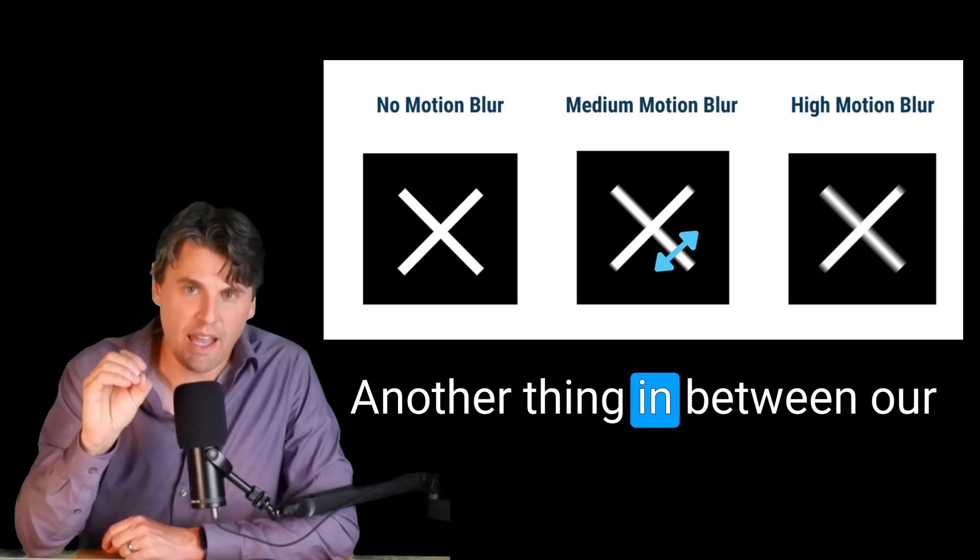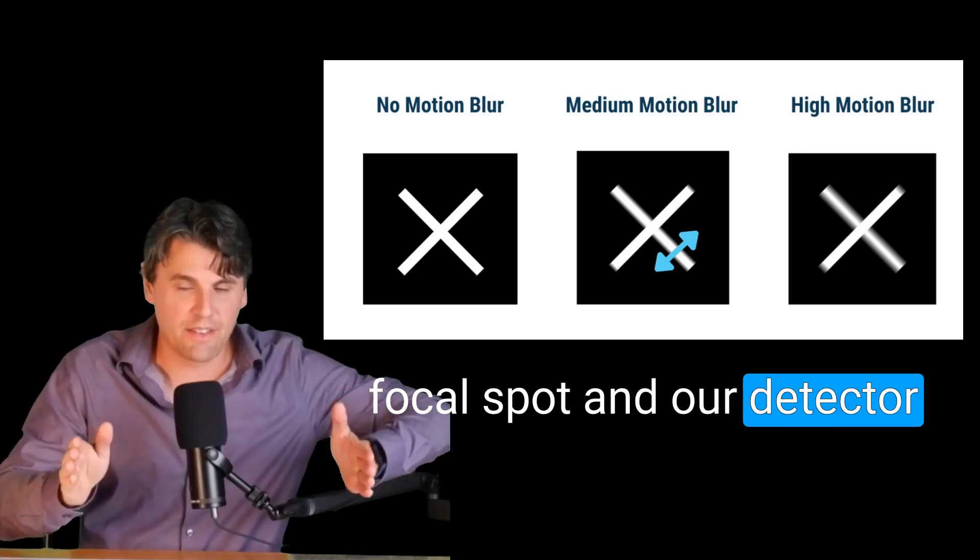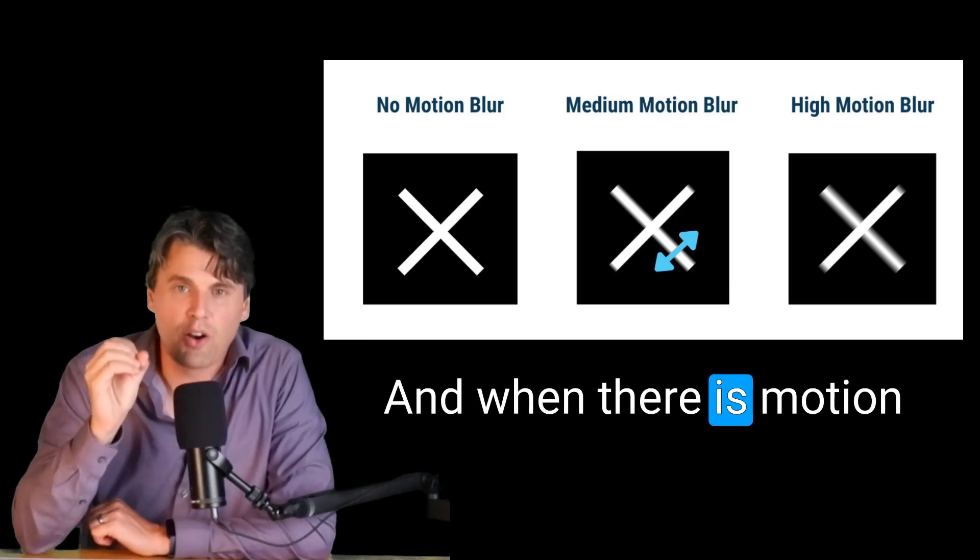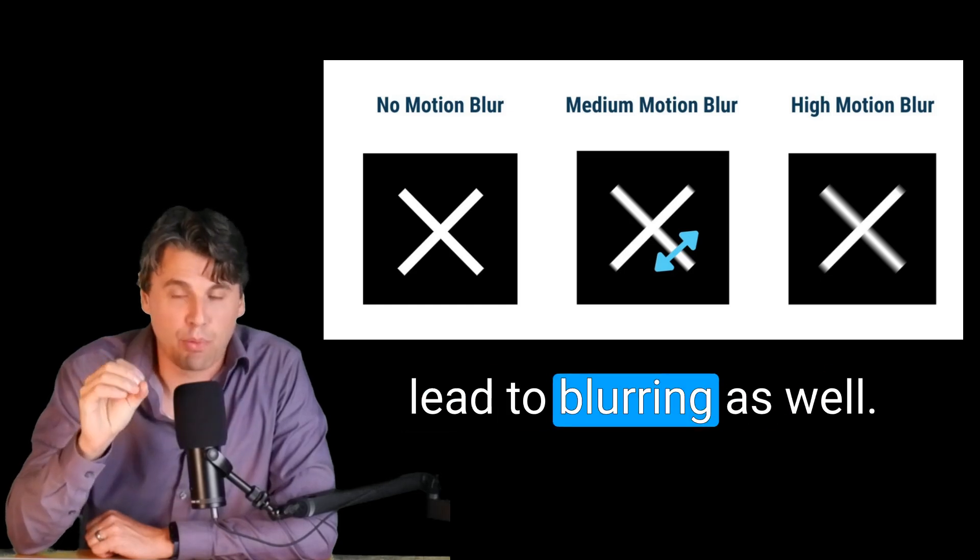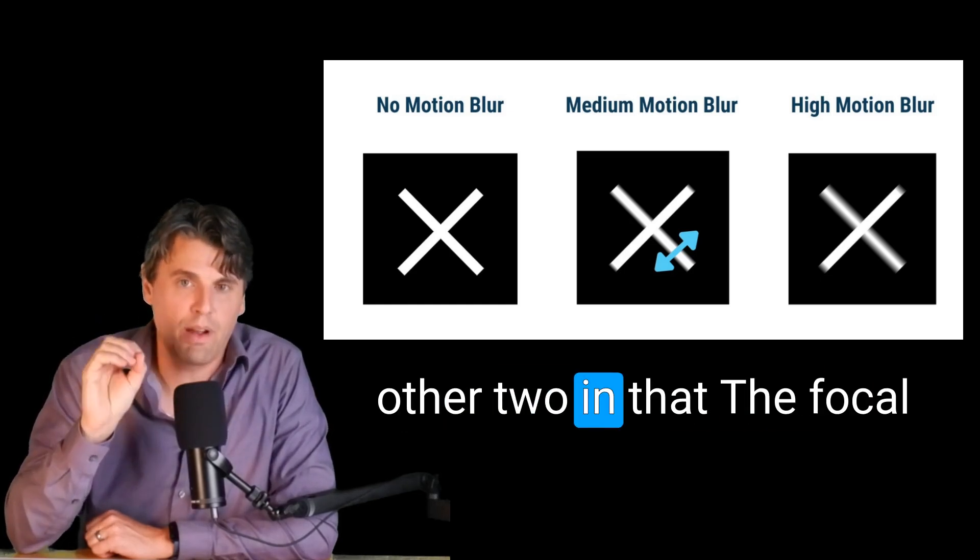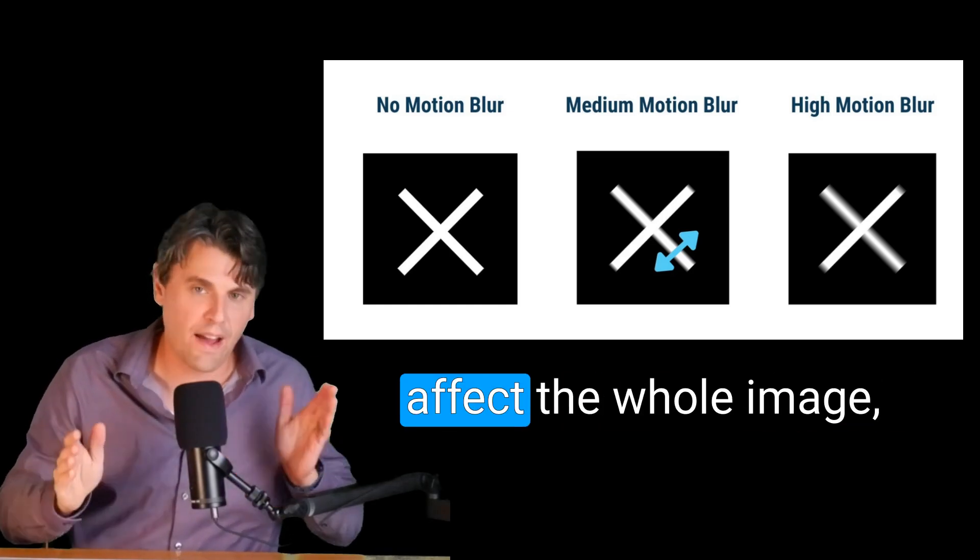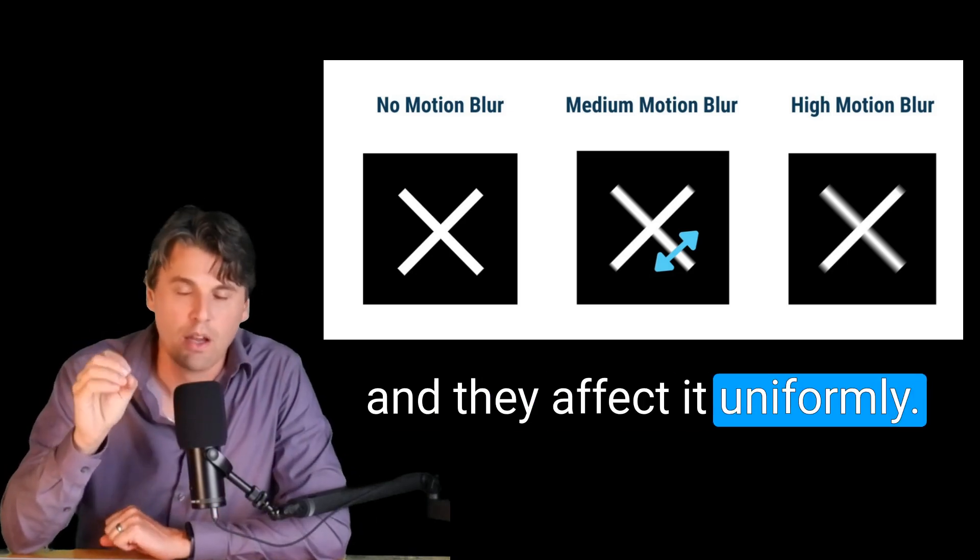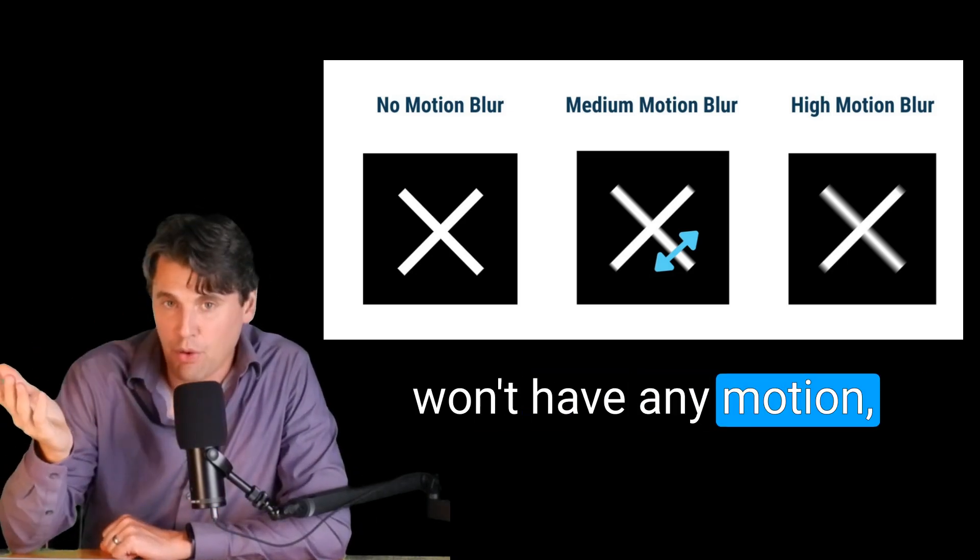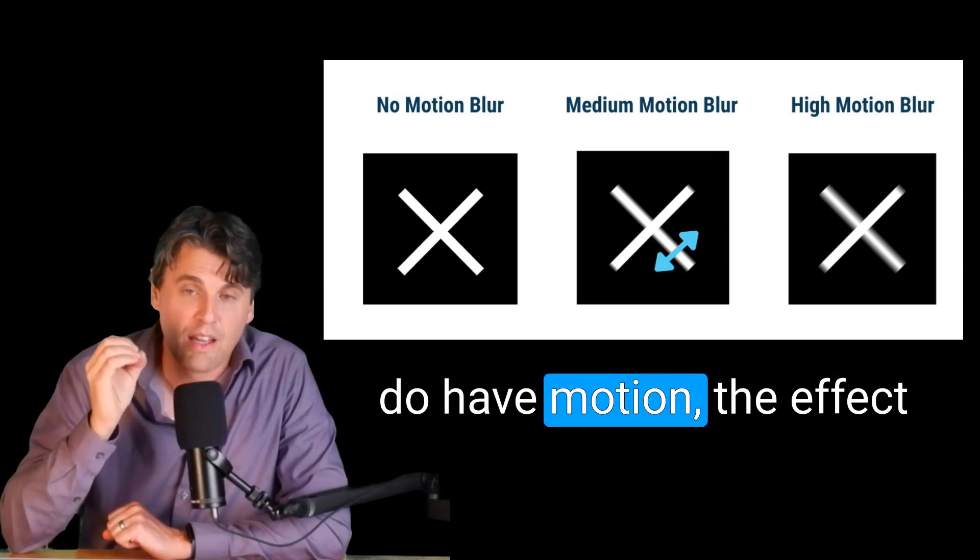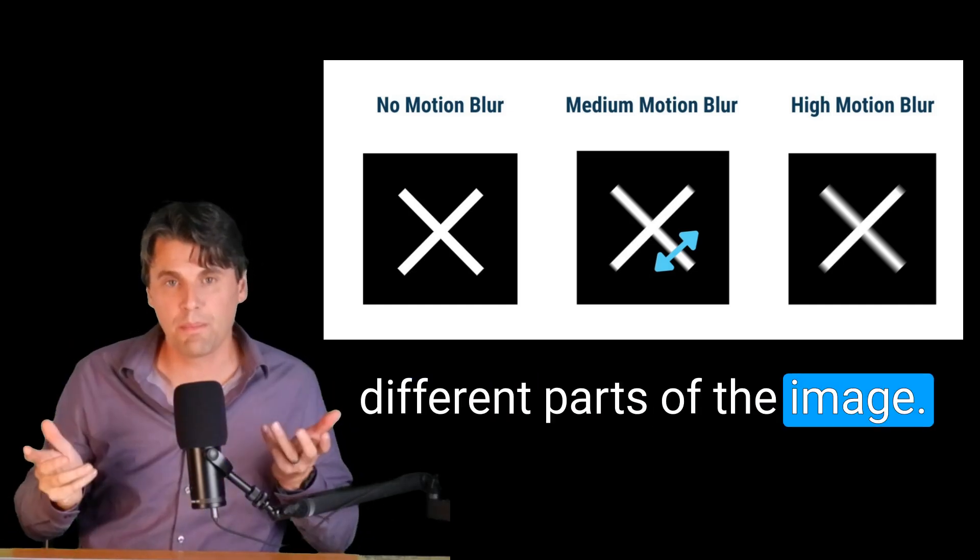Another thing in between our focal spot and our detector is actually the object itself. And when there is motion within the object, that can lead to blurring as well. This is different from the other two, in that the focal spot and detector, they affect the whole image, and they affect it uniformly. Motion, sometimes you won't have any motion. And sometimes when you do have motion, the effect is actually different for different parts of the image.